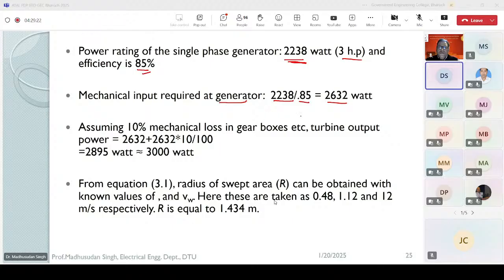But between the turbine and generator, we also use a gearbox. So the gearbox also has some efficiency issue. If we consider the loss in the gear to be maybe around 10%, then the additional watt which needs to be generated by the turbine is 10% of the mechanical input. So this comes to around 3000 watt or 3 kilowatt. So we understand that with given motor ratings and its efficiency, we can decide how much mechanical power we are expecting from the turbine.